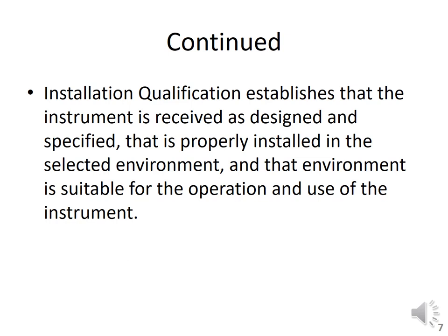Now, this is the continuation of the previous slide, right? Installation qualification establishes that the instrument is received as designed. We have discussed, right? And as specified. That it is properly installed in the selected environment. The environment should be selected carefully, and then the installation should be done properly. So you have to check this point as well, and that the environment is suitable for the operation and use of the machine.